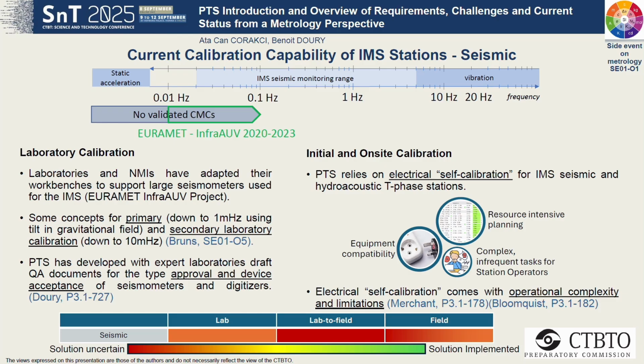For the IMS seismic stations, the frequency range of interest is from 20 millihertz to 5 hertz, and there are no validated CMCs at frequencies below 0.1 hertz. On the laboratory calibration side, with the recent Euramet InfraAUV project completed in 2023, laboratories and NMIs have adapted their workbenches to calibrate large seismometers, because normally they calibrate accelerometers on their workbench, but this adaptation was done during this project. Some concepts are being studied for primary and secondary laboratory calibrations.